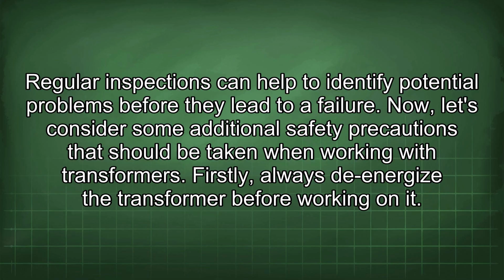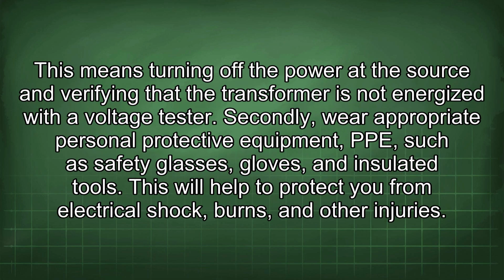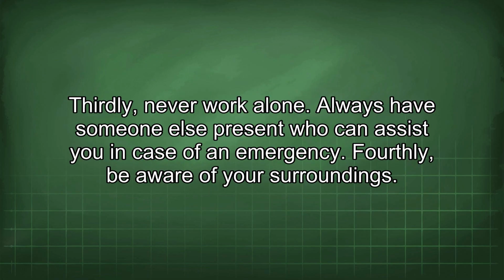Now, let's consider some additional safety precautions that should be taken when working with transformers. Firstly, always de-energize the transformer before working on it. This means turning off the power at the source and verifying that the transformer is not energized with a voltage tester. Secondly, wear appropriate personal protective equipment, PPE, such as safety glasses, gloves, and insulated tools. This will help to protect you from electrical shock, burns, and other injuries. Thirdly, never work alone. Always have someone else present who can assist you in case of an emergency.